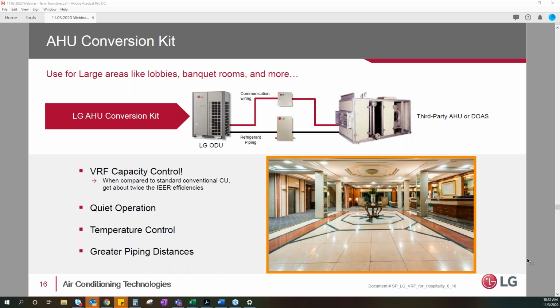Another option we've got on the VRF side for heat pumps is we can take an existing older air handler and convert it to VRF. We've proposed this on a number of churches where they wanted to add air conditioning. By adding coils to their air handler and putting a variable frequency drive on their motor, we're able to give them an incredibly efficient system for both the heating and the cooling side. What we found in many of these is the energy savings on the heating side has offset the cost of adding the air conditioning. So even though they've added air conditioning, their overall annual budget for energy doesn't change much. And that's been a tremendous advantage for a lot of churches and schools in particular with these big old air handlers.